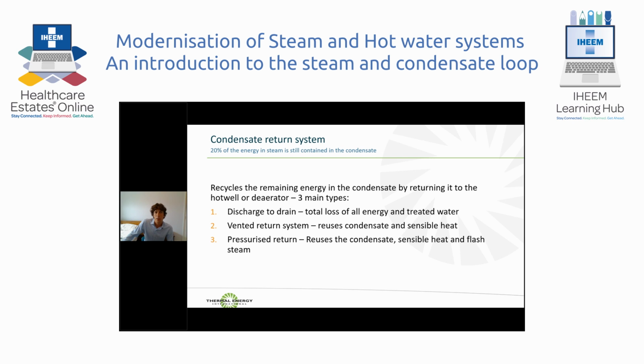We have 3 options for our condensate return systems. One is to discharge to drain, where we get total loss of all energy and treated water. This is very uncommon in the UK due to high energy costs. We have a vented return system, which reuses the condensate, reducing water treatment costs, and we also get the sensible heat content of the condensate. We can also look at pressurized return systems. They reuse the condensate, the sensible heat, and also recover the flash steam.